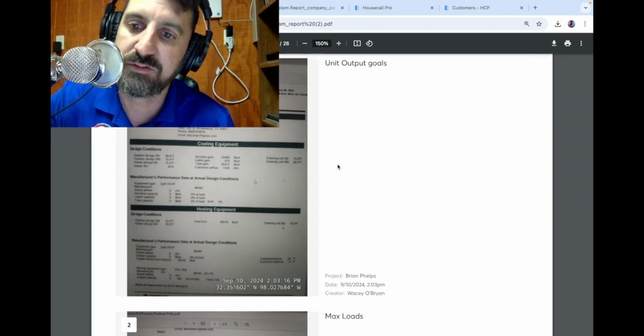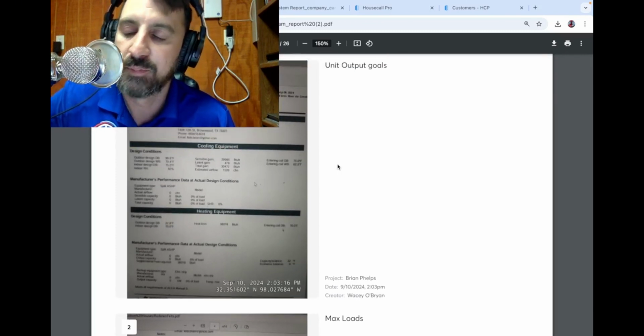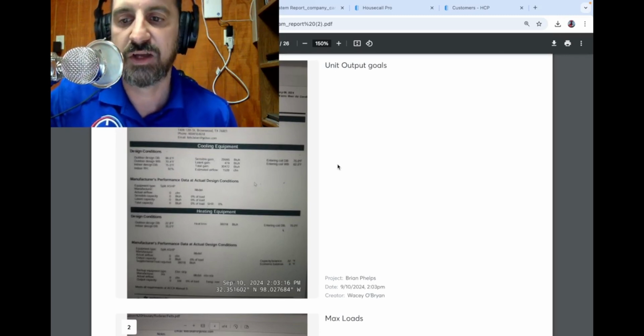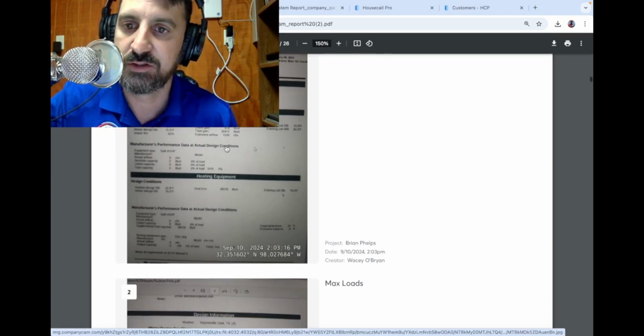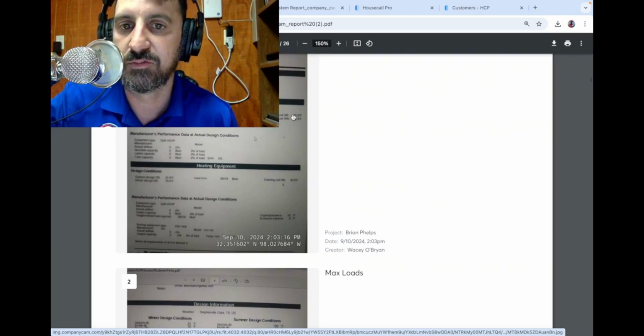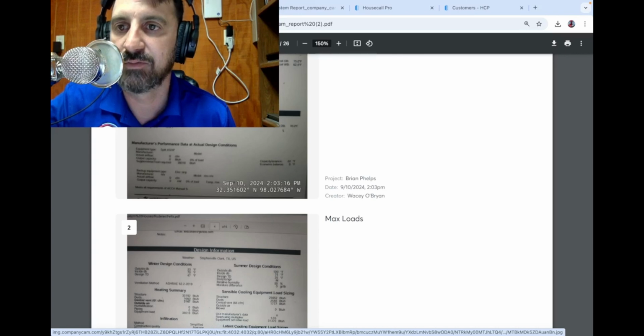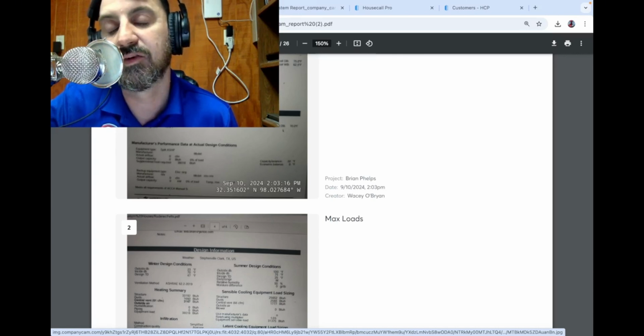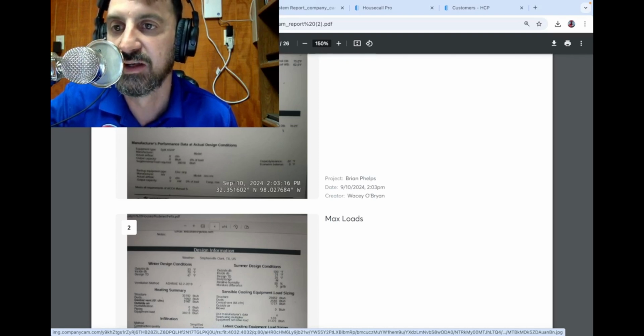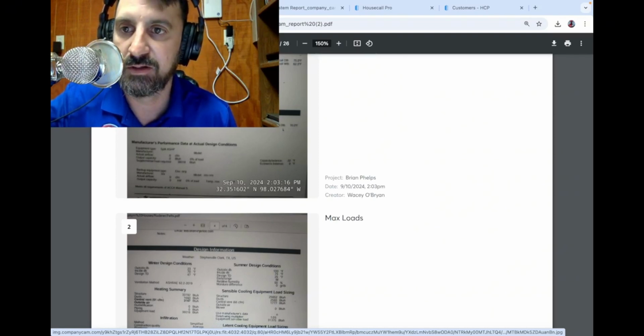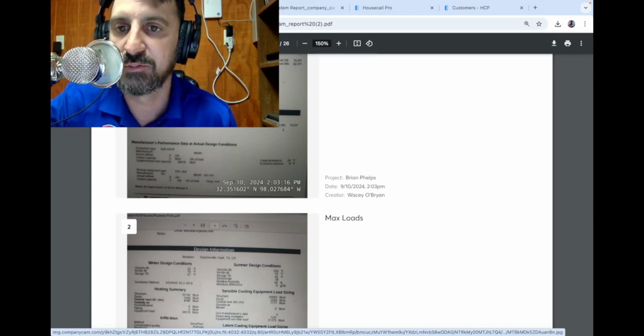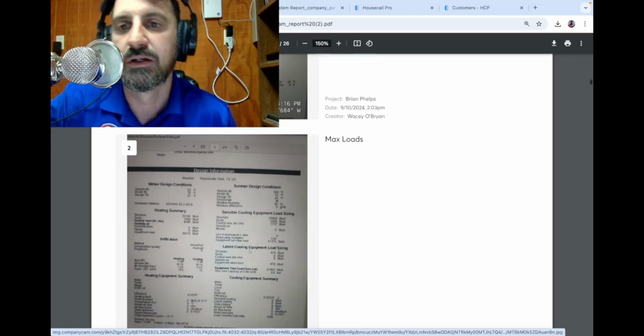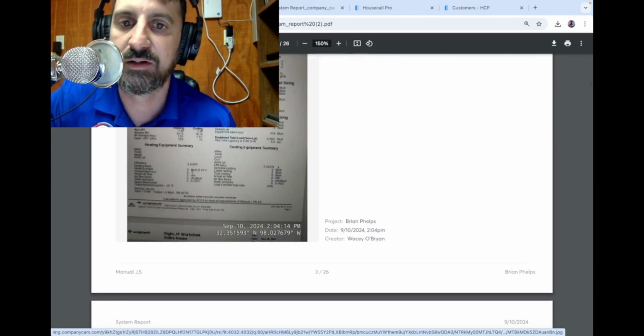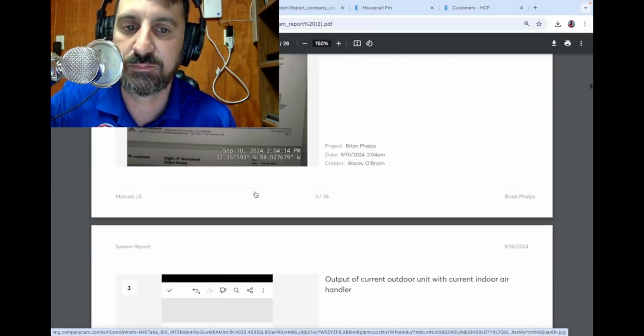I didn't assign equipment to this because basically we don't know exactly what we're going to do with the house yet, but this first photo just shows us what our sensible and latent gain is, what the airflow and all of that stuff is, shows you where our temperatures are set for our design, and you can see the outdoor design temp we're using in our area for the average max is 99.6. All of that fun stuff. And here we're shooting for a 50% relative humidity level. Goes through the design conditions, tells you how much you should be aiming for.